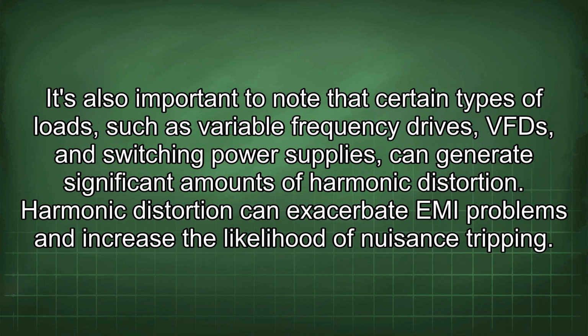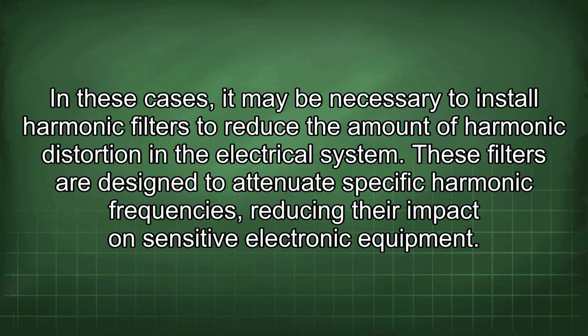It's also important to note that certain types of loads, such as variable frequency drives (VFDs) and switching power supplies, can generate significant amounts of harmonic distortion. Harmonic distortion can exacerbate EMI problems and increase the likelihood of nuisance tripping. In these cases, it may be necessary to install harmonic filters to reduce the amount of harmonic distortion in the electrical system. These filters are designed to attenuate specific harmonic frequencies, reducing the impact on sensitive electronic equipment.